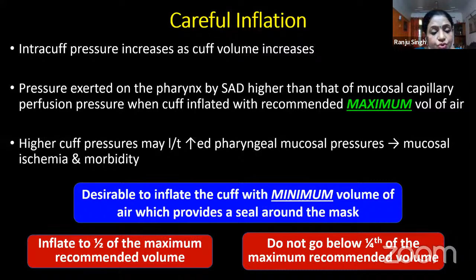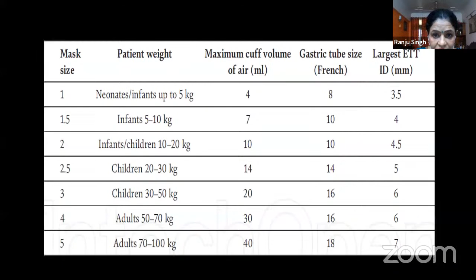For a Pro Seal, a common mnemonic that eases memory of the maximum cuff volume of air is, in larger sizes, you take the size number, that is, if it's a size 3 device, minus 1 from that and multiply by 10. So 3 minus 1 is 2, 2 into 10 is 20. 20 is the maximum cuff volume in that size device. For a size 4, 4 minus 1 is 3, 3 into 10 is 30. That is the maximum amount in the Pro Seal. Occasionally, the examiners may ask you this.